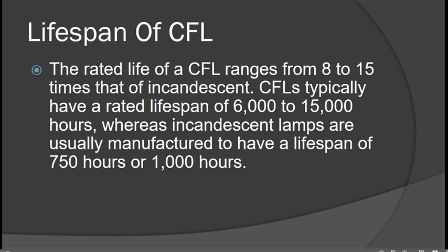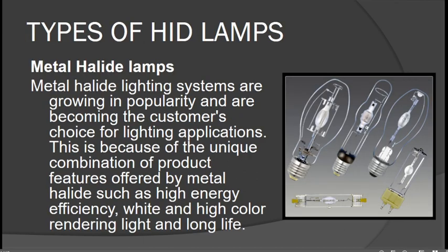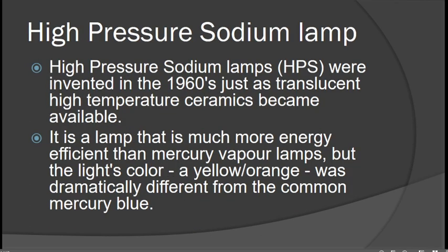High Intensity Discharge (HID) lamps produce lighting by means of an electric arc between tungsten electrodes housed inside a translucent or transparent fused quartz or fused alumina arc tube. Types of HID lamps include metal halide lamps, which are growing in popularity due to their high energy efficiency, high color rendering, and long life.